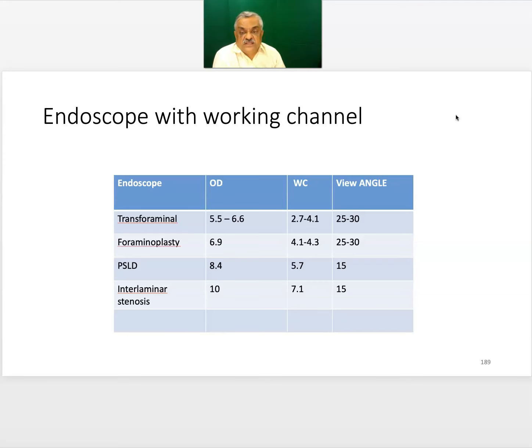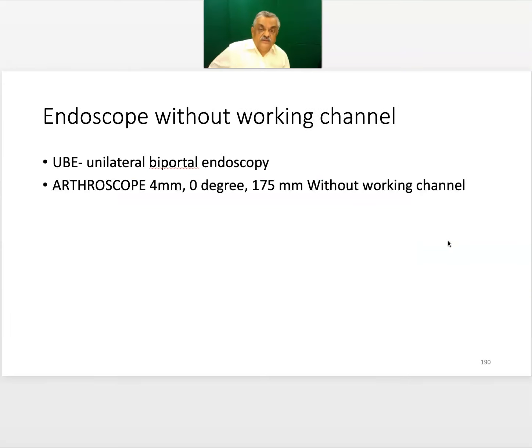Now endoscope with working channels, we have other endoscopes for interlaminar stenosis, 10 millimeter outer diameter, 7.1 working channel, 15 degrees, PSLD scope, 8.4 outer diameter, 5.7 working channel, 15 degrees. Our foraminoscopy or transforaminal, the outer diameter is 6.9, working channel is 4.1 or 3.6, and the angle varies from 25 to 30. The endoscope are also available without working channel, mainly the arthroscope, which is 4 mm, 0 degree, 17.5 centimeters without working channel. This is used in UBE or unilateral biportal endoscopy by the surgeons.